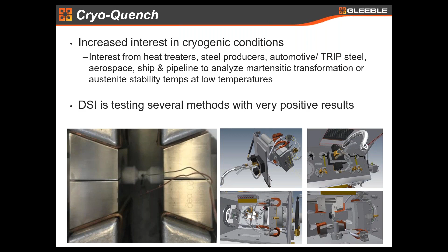We have, here's some data. So this test, we went from 1100 C down to -175. Again, you can see some of the setup information for our Gleeble users. That makes sense. You can see the specimen type. Again, we use ISO-Q method, stainless steel grips. It was a 10 millimeter full contact specimen. We went down from 1100 down to -60 C in 12.5 seconds, and in 26 seconds we went down to -172. So I think that's pretty impressive.